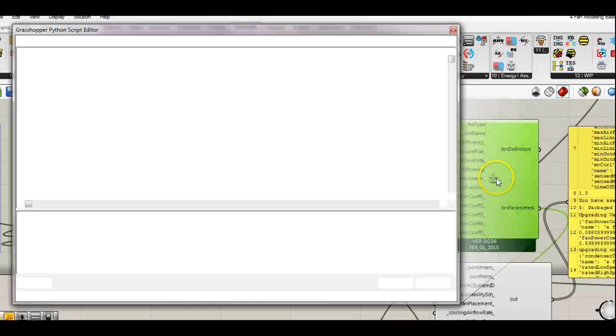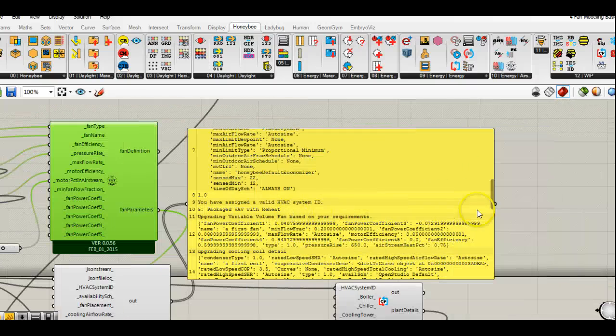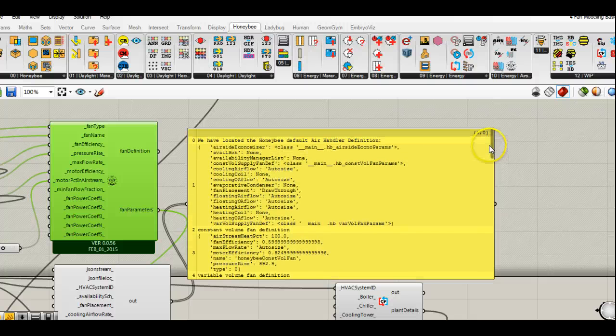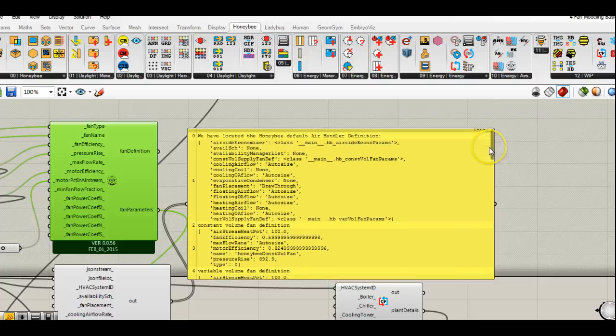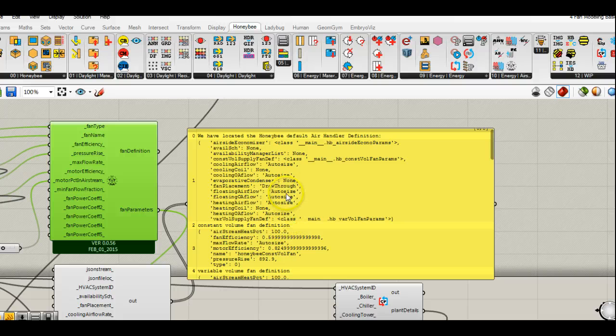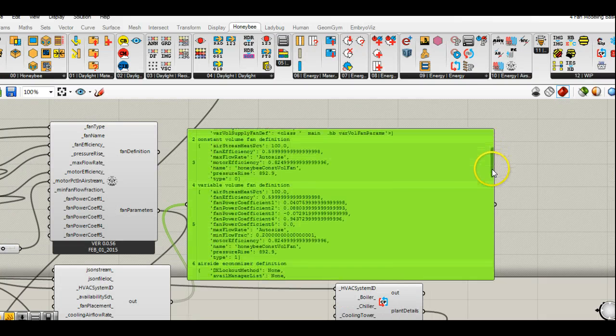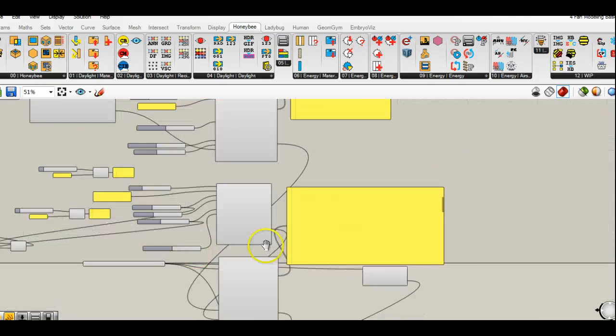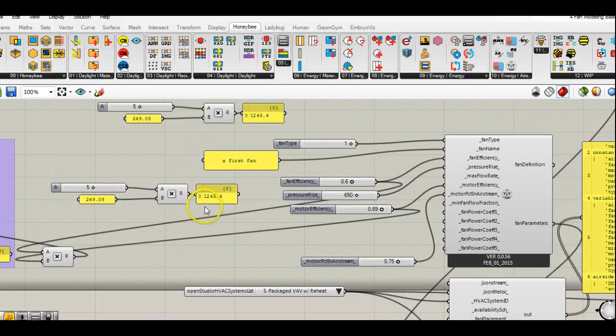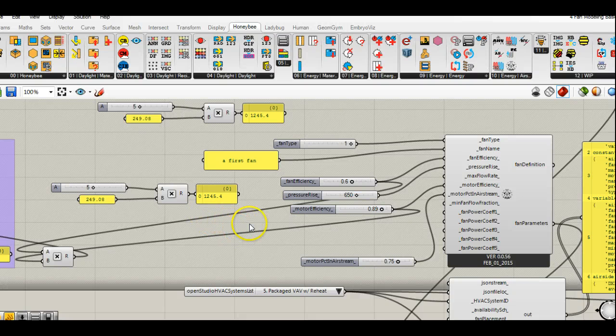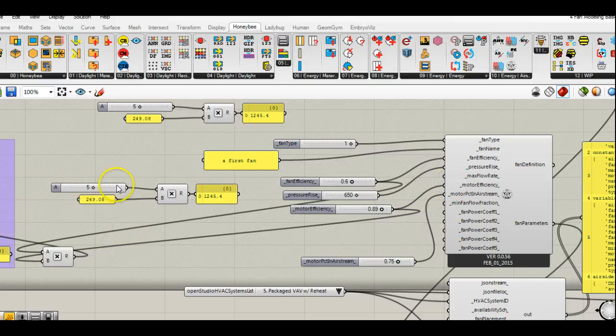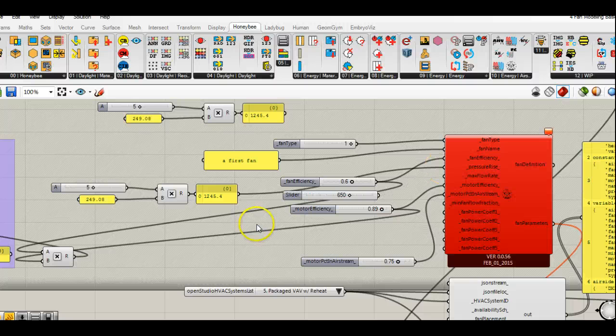The Honeybee default is also the EnergyPlus default if nothing is used. You can see here that the Honeybee default for variable volume fans says that the pressure rise is 892 pascals. That's about almost 50 percent higher than that value. So if you're doing this for LEED modeling and you are an engineer, don't use the defaults. I would say try and figure out what your pressure drop is through your system, convert it to pascals, and go ahead and plug that in for pressure rise here.